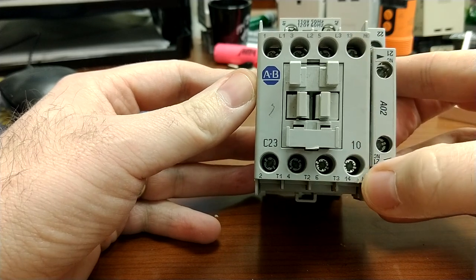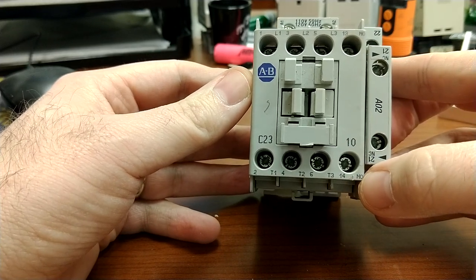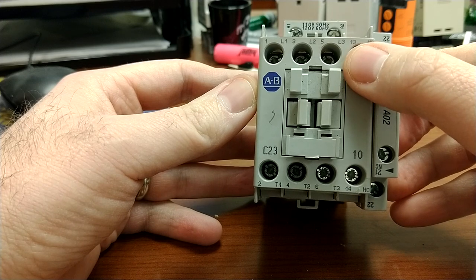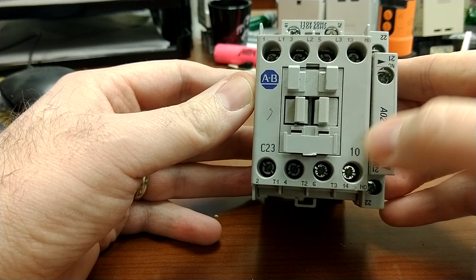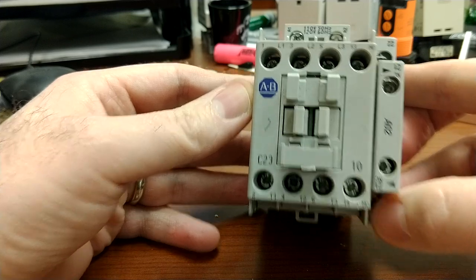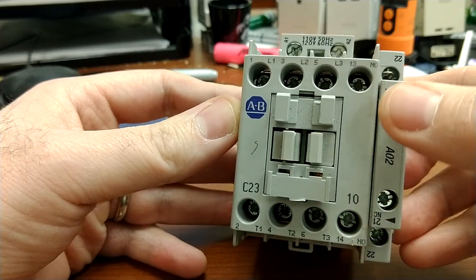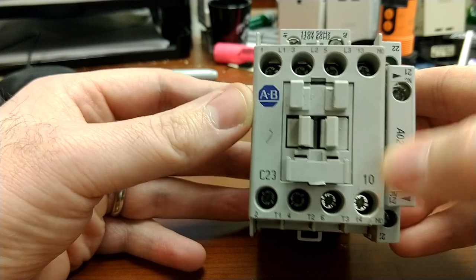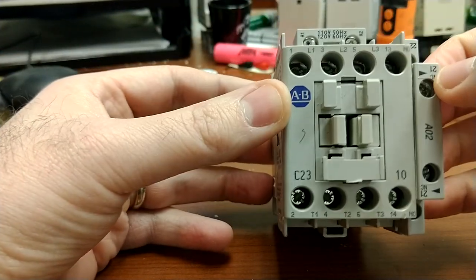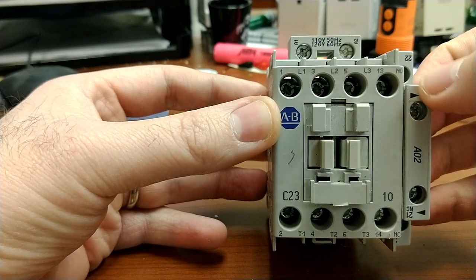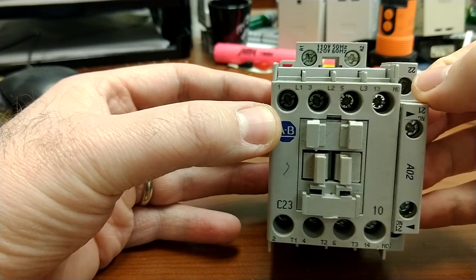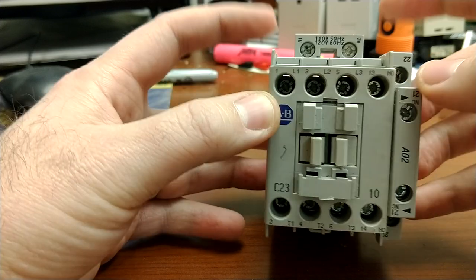Now, in this case, you'll see another pole, but if you look closely, the 1, 3, 1, 4, normally open, you can see closely, it says normally open, normally open. These are relay contacts on the side to feed back to a PLC if a relay is engaged.